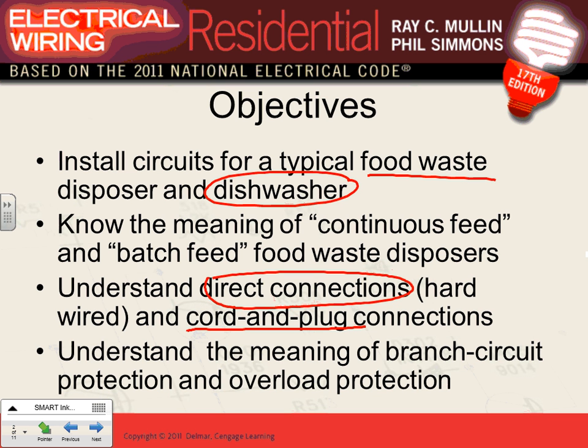If you decide to hardwire your dishwasher, typically they are plug-in, you have to keep in mind that you have to provide a disconnect. And the disconnect for them could be, because the amp is small and they're single phase, as simple as a snap switch right there. You bring the hot into the snap switch, and out of the snap switch to feed the disposal, and you just met the code. Can I have everybody give a thumbs up that we understand the difference: direct connection, you need a snap switch for these single phase appliances; plug them in, you do not need a snap switch for them. Cool? So that's basically the most important thing.